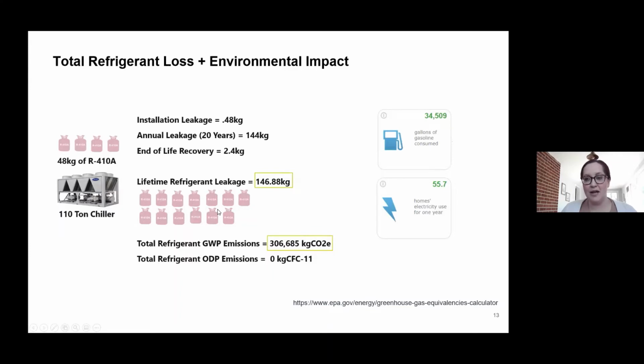So if you just think about the number of canisters of refrigerant, that I think these are about 25 pounds each, that's how much refrigerant you're actually leaking to atmosphere throughout its 20-year life. If we multiply that by the 2,000 number, you're looking over 300,000 kilograms of CO2. Converting that using the EPA calculator to gallons of gasoline, almost 35,000 gallons of gasoline is an equivalency here, and 55 homes' electricity use for a year. So the impact's huge just for that one chiller for 20 years.